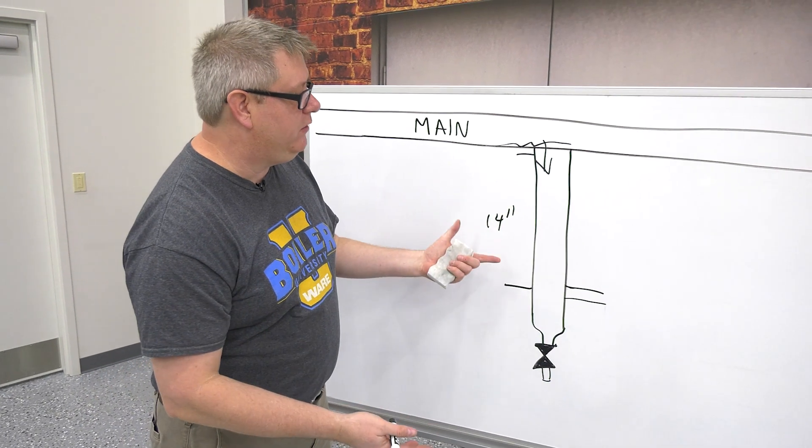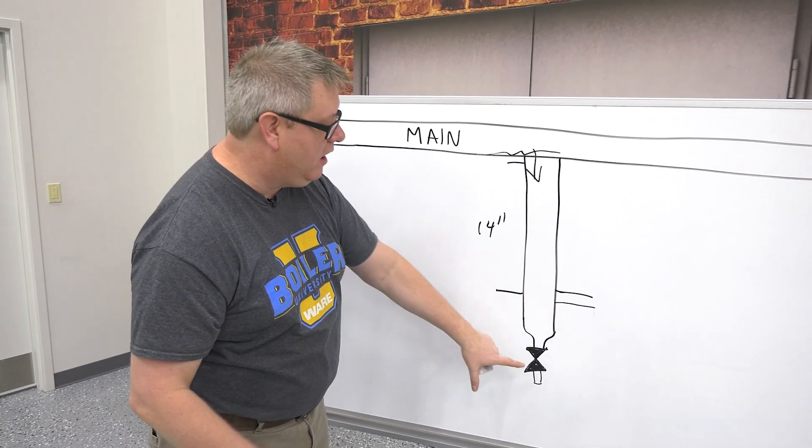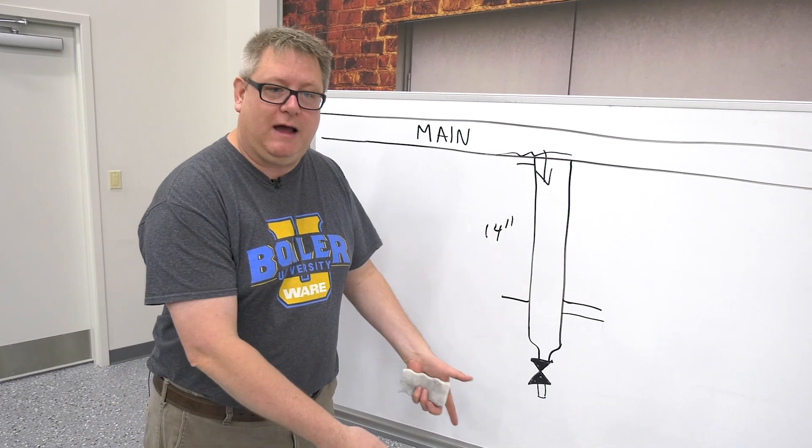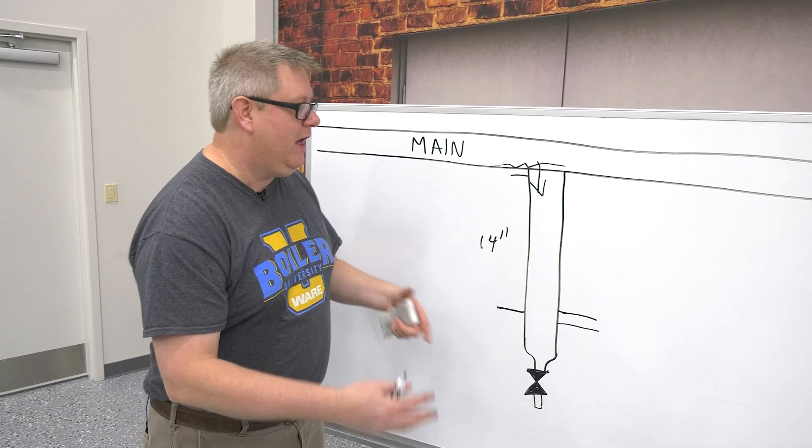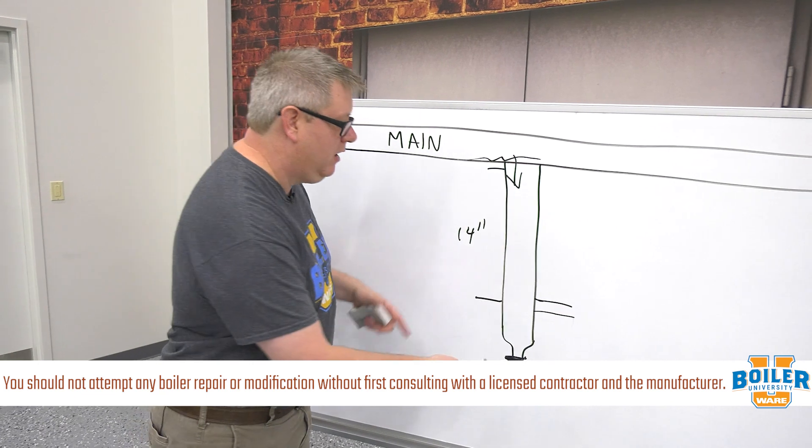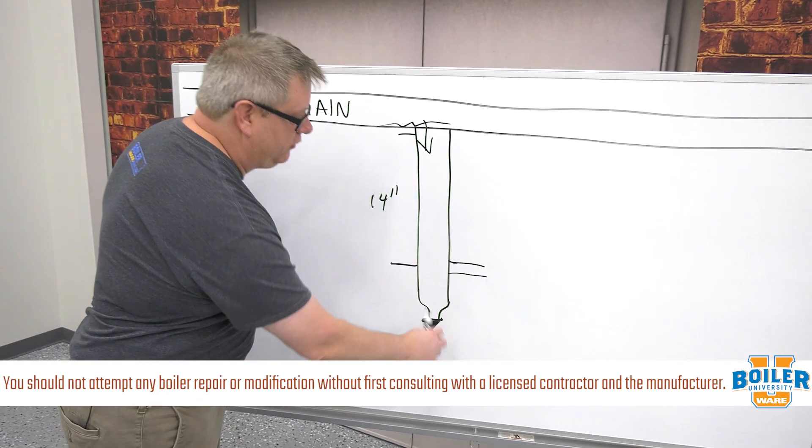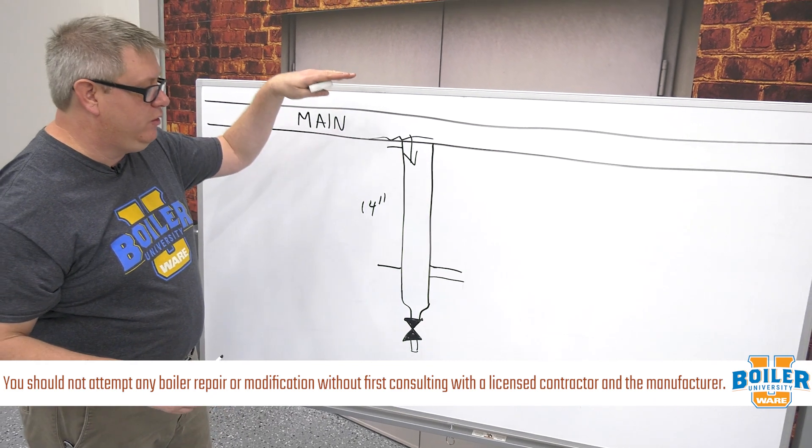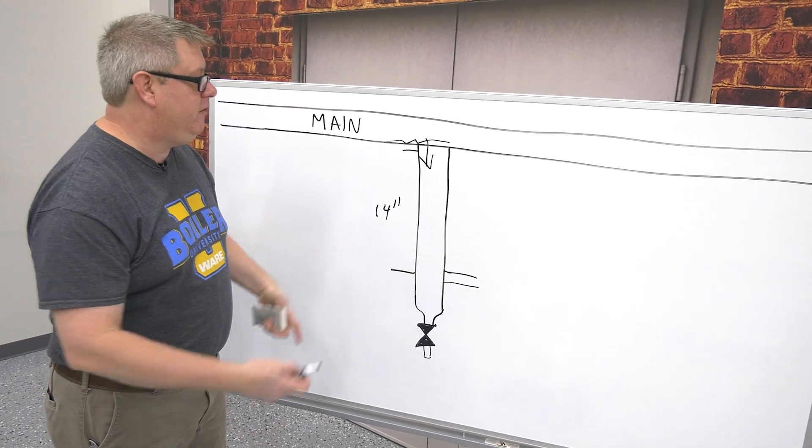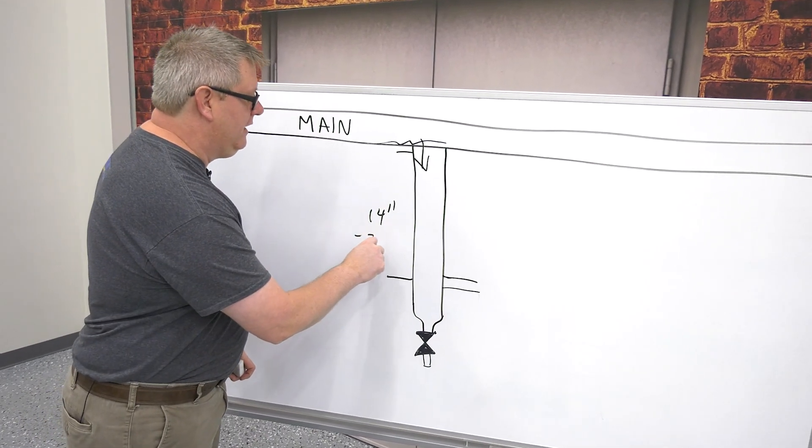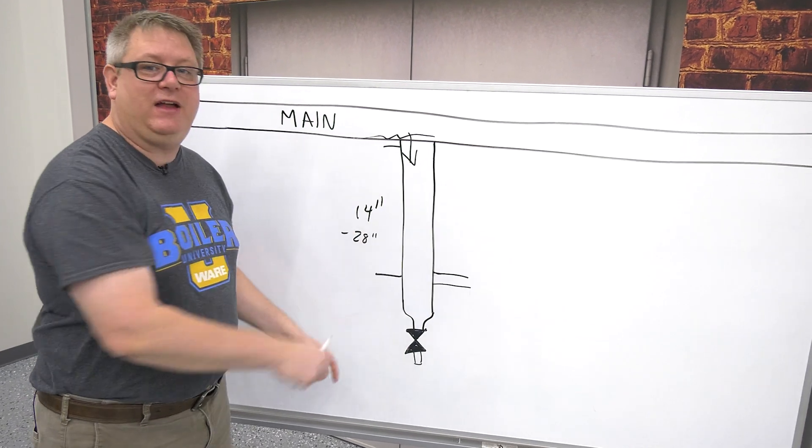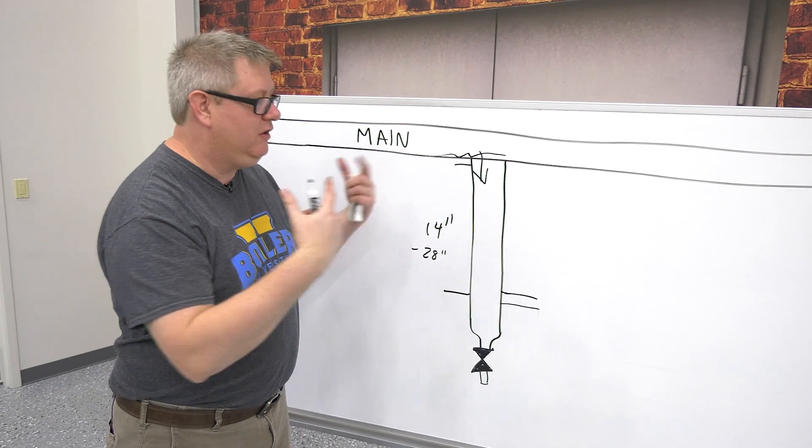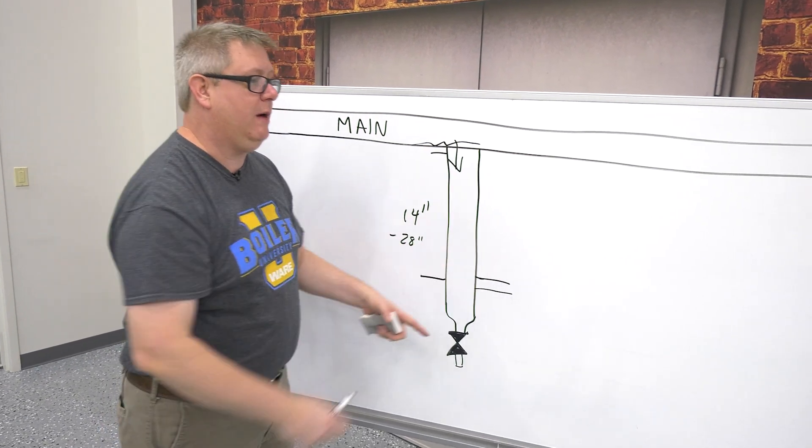A manual startup on a system means when I shut the system down, I may go around and open these drain valves to remove, allow condensate to drain from the system. And as the system comes back up, when steam starts coming out, I will close those. In an automatic system where we want to do it all without any operator intervention, we'll use a 28 inch drip leg, and that just gives us additional volume to accumulate condensate until we get the system pressure to push it through our trap.